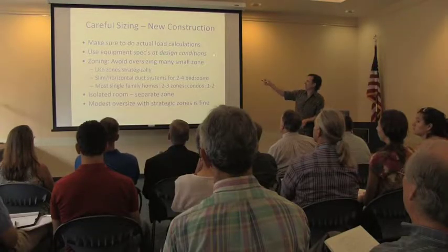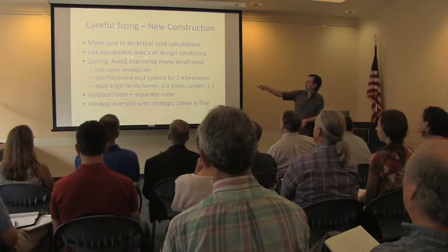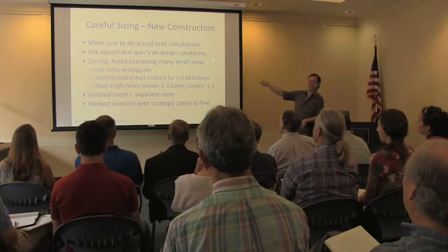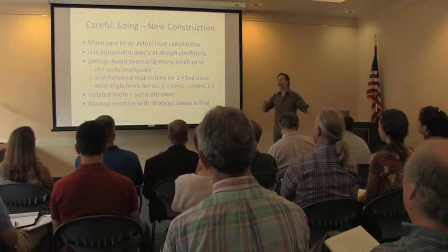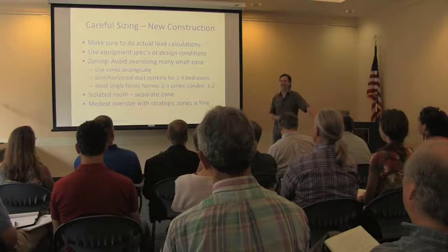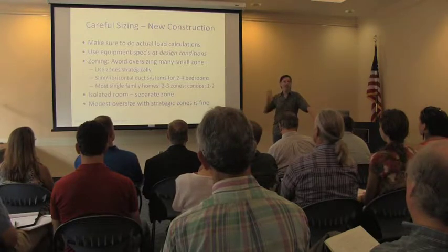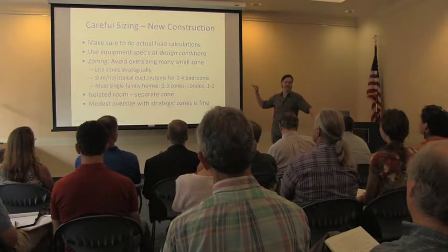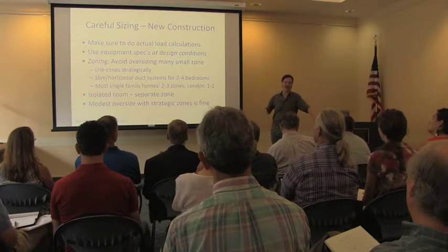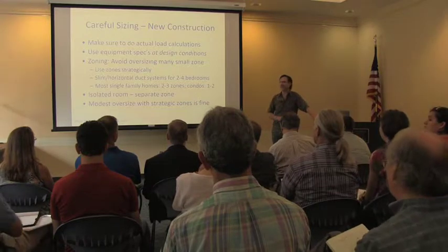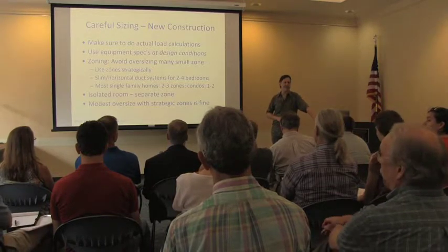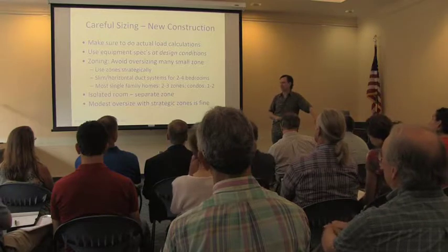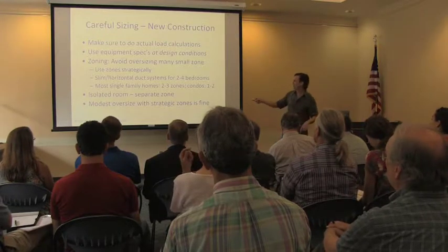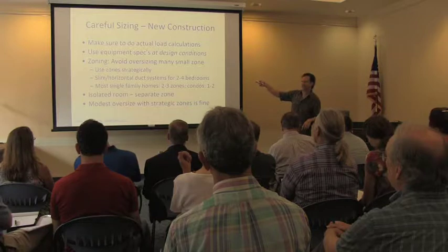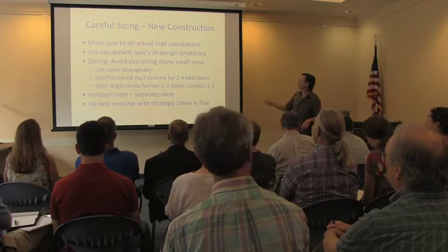And this is a standard way to do load calculations. You want to make sure that you use the equipment specs at design conditions. Don't just say, oh, it's a 2-ton system that's rated at 24,000 BTUs per hour. That's the nominal size. It's really, really important to make sure you look at the actual information for that product. And that's one of the places where that 5-degree performance that's in the NEEP listing is a key area that you can look at and verify that you're using the right information.